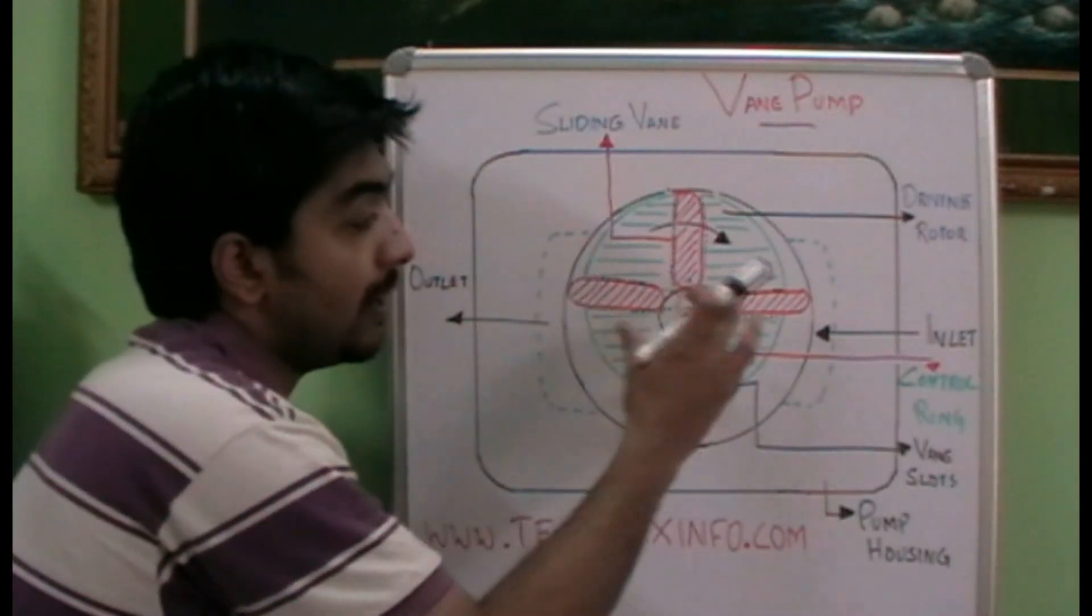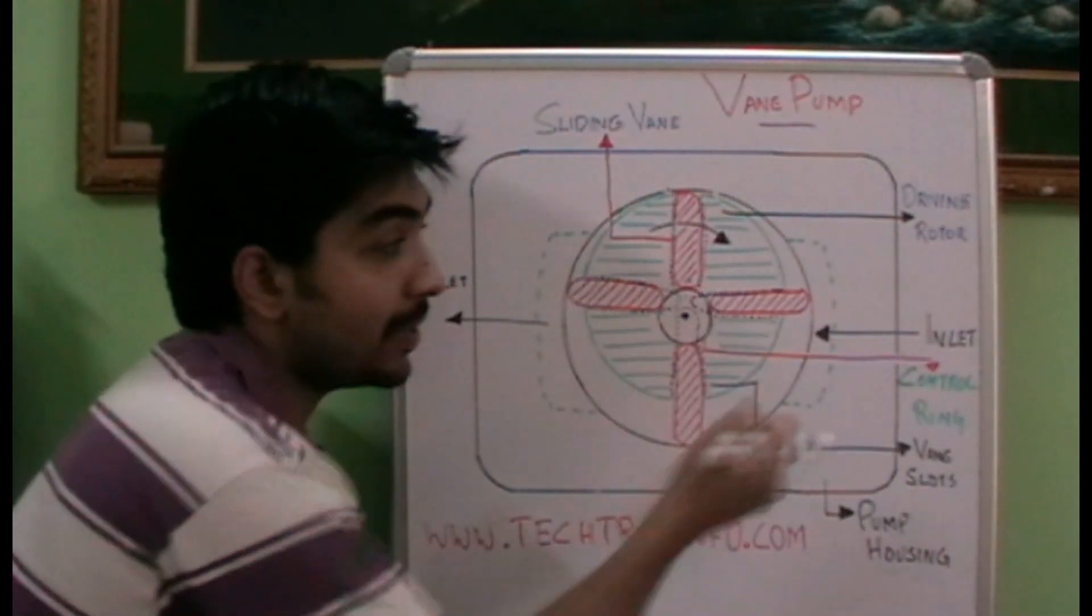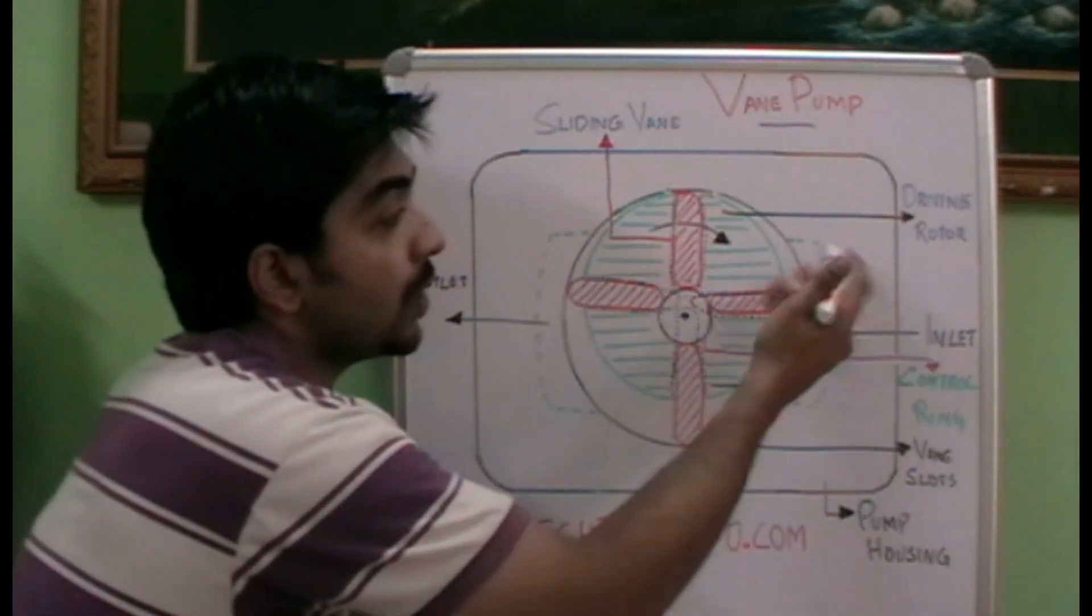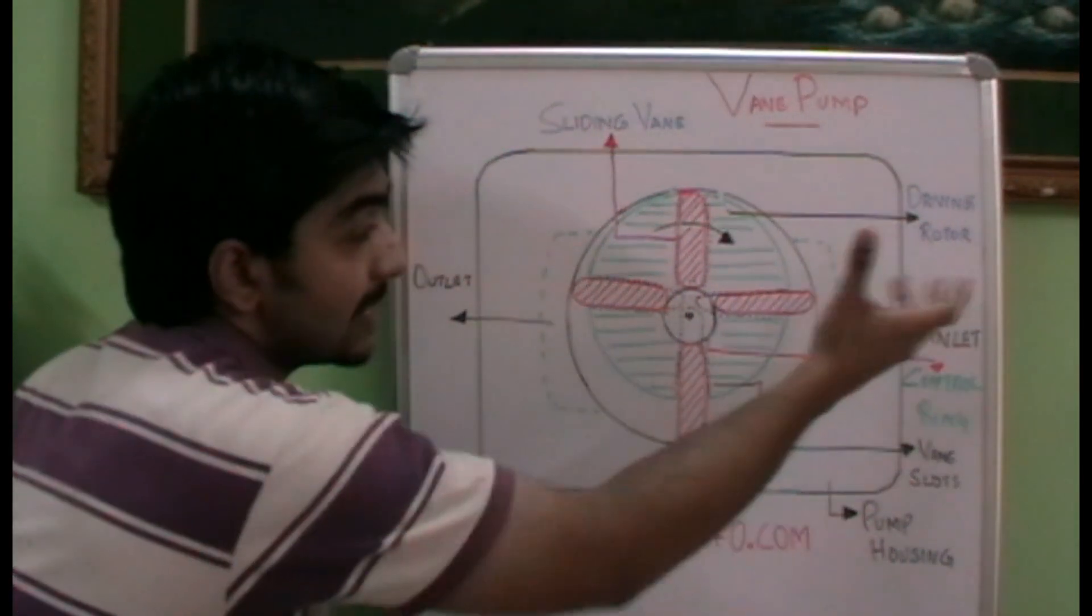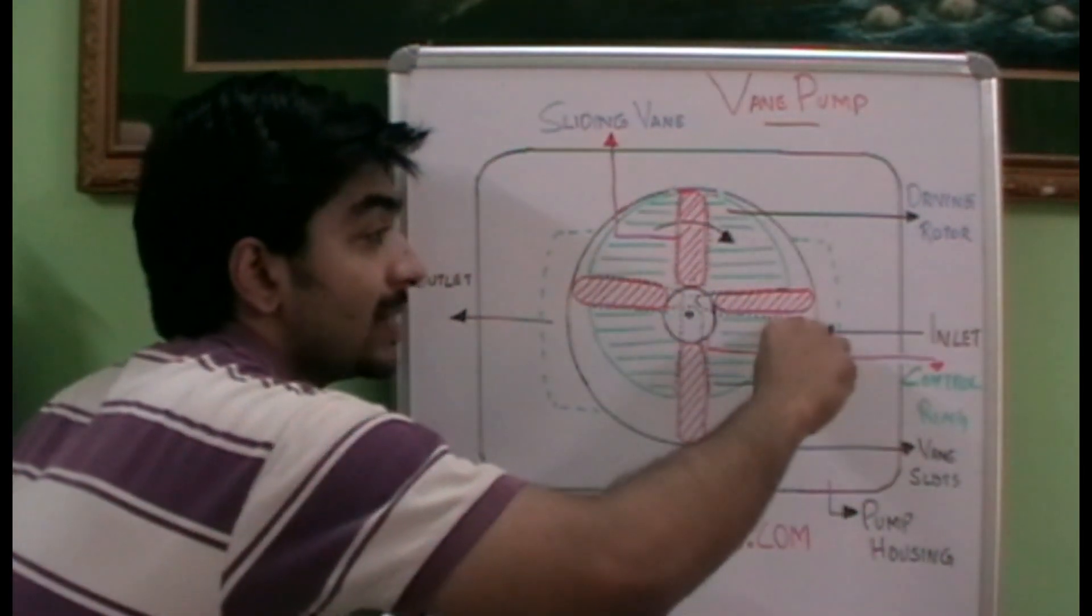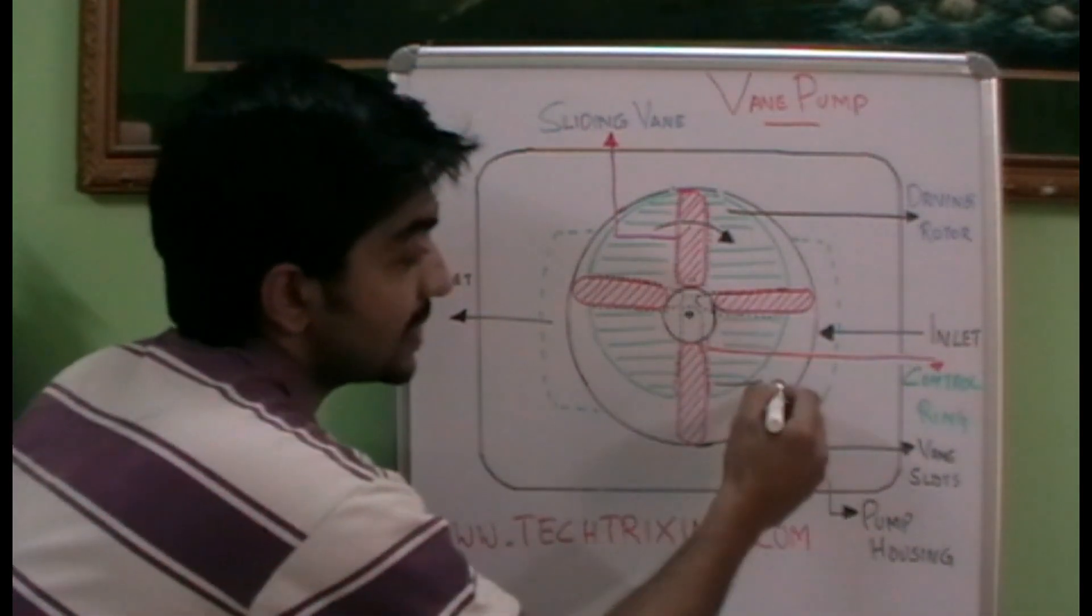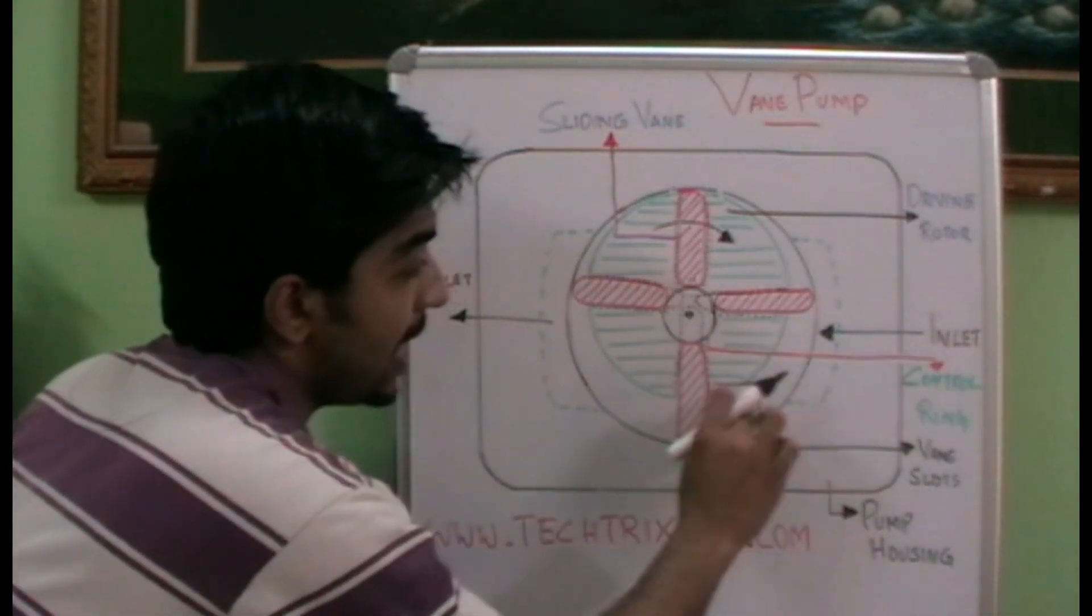So as it is rotating in clockwise direction, here the area is less and gradually it is increasing. So as suction is happening at this port, the oil or the fluid is sucked from this port and is swept by the help of these vanes which is trapped inside this container.